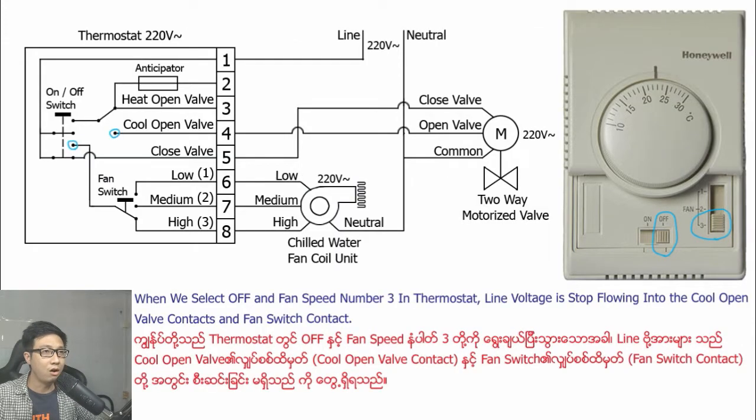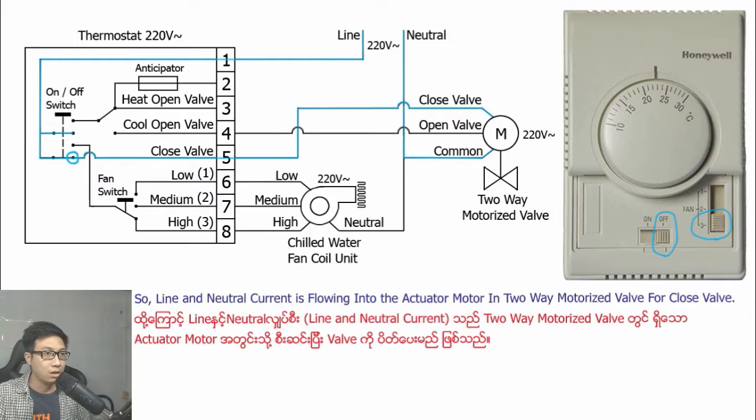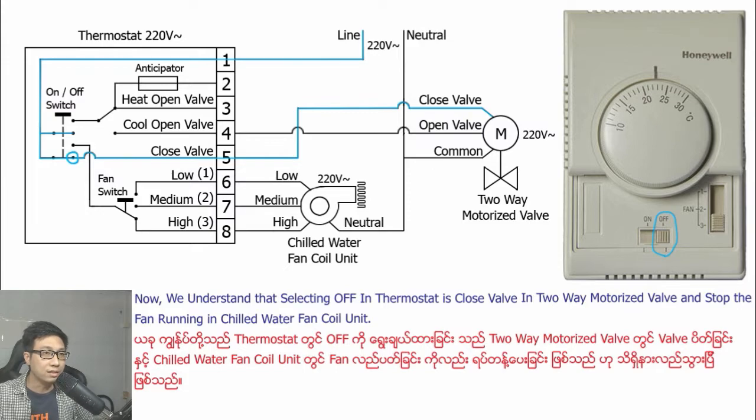When we select off and fan speed number three in the thermostat, line voltage stops flowing into the cool open valve contact and fan switch contact. But line voltage is flowing into the closed valve contact. So line and neutral current is flowing into the actuator motor in the two-way motorized valve for the closed valve. Sliding to off in the thermostat closes the two-way motorized valve and stops the fan in the chilled water fan coil unit.